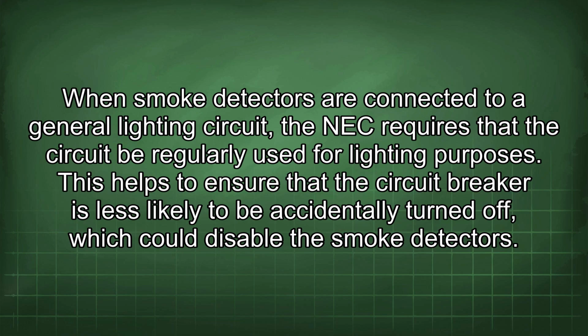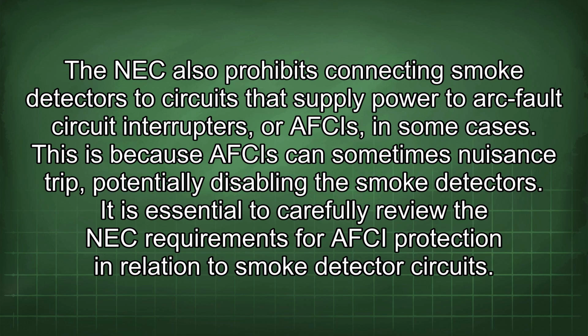disable the smoke detectors. The NEC also prohibits connecting smoke detectors to circuits that supply power to arc fault circuit interrupters, or AFCIs, in some cases. This is because AFCIs can sometimes nuisance trip, potentially disabling the smoke detectors. It is essential to carefully review the NEC requirements for AFCI protection in relation to smoke detector circuits.